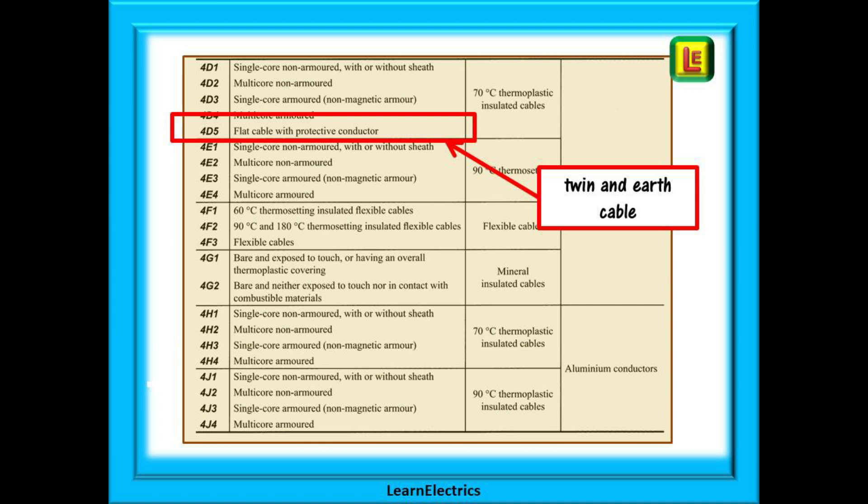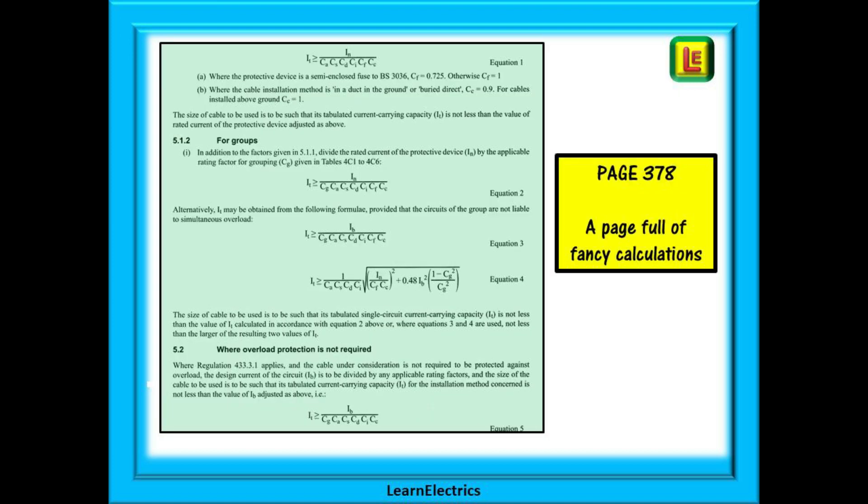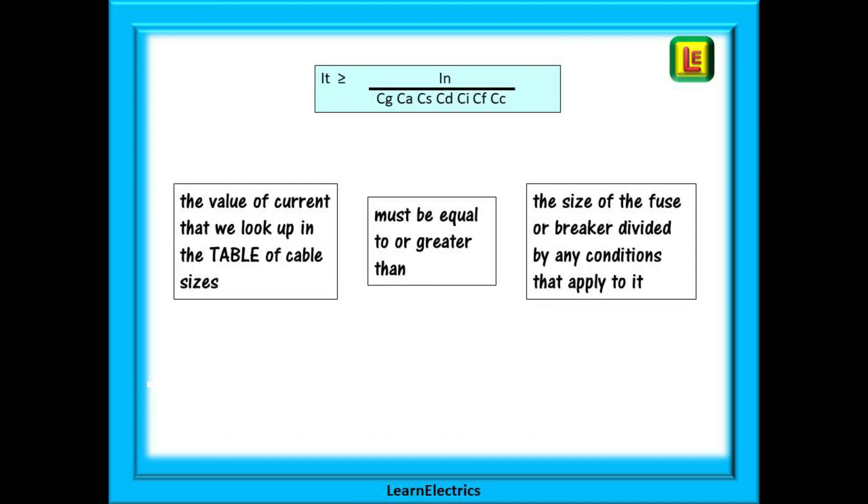On page 378 we will find a whole page of fancy calculations for working out cable sizes for all these different conditions and rating factors. Don't worry we are going to make it very easy. If we take the first equation it looks like this. What does each part actually mean? The first symbol IT is the tabulated current. I for current, T for tabulated.